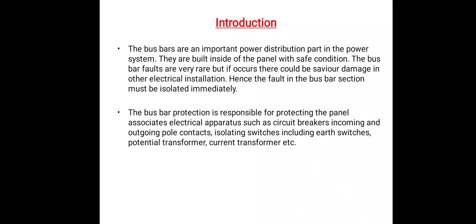The bus bars in electric power stations and substations are one of the most vital elements. Although with the advent of modern design methods, the probability of occurrence of fault has been reduced to negligible. But if a fault occurs on a bus bar, considerable damage and disruption of supply will occur unless some form of quick-acting automatic protection is provided for isolation of the faulty bus bar. The bus bar protection is responsible for protecting the panel associates, electrical apparatus such as circuit breakers, instrument transformers, and other heavy equipment.